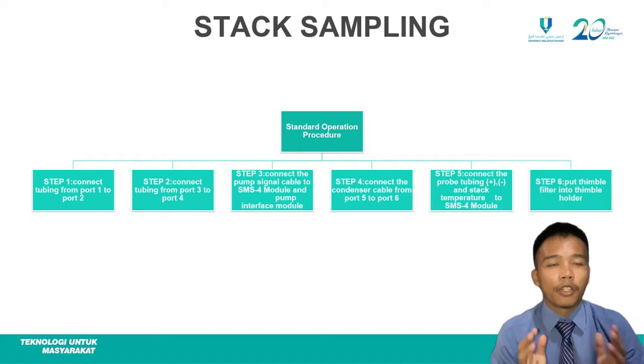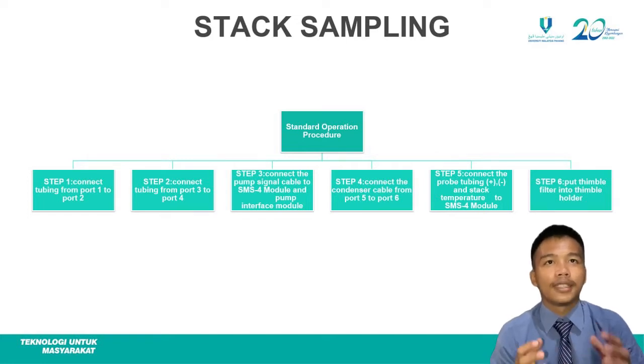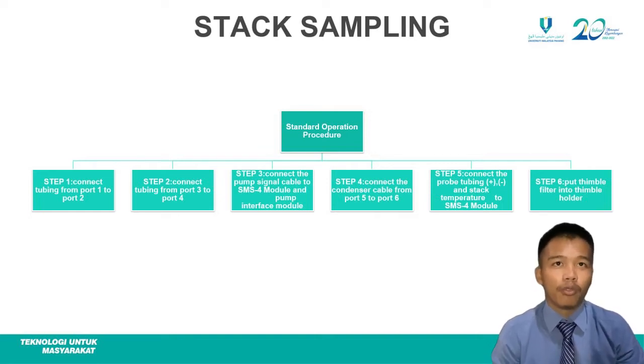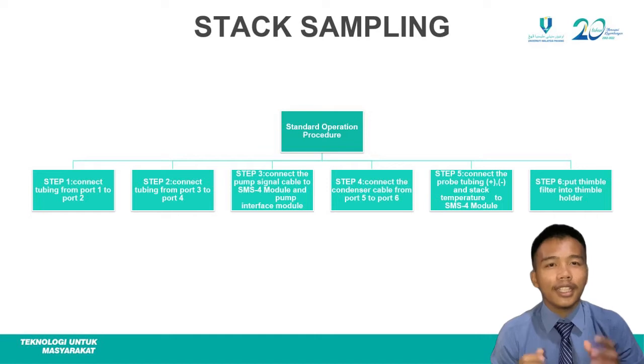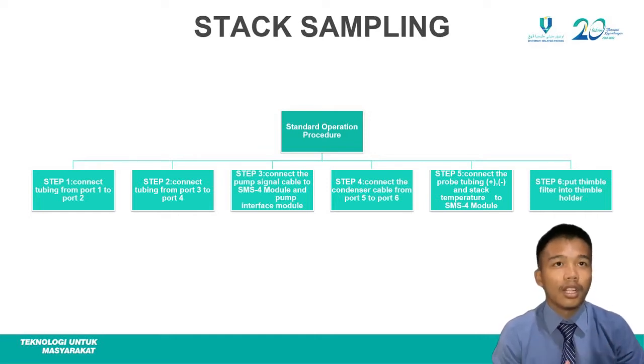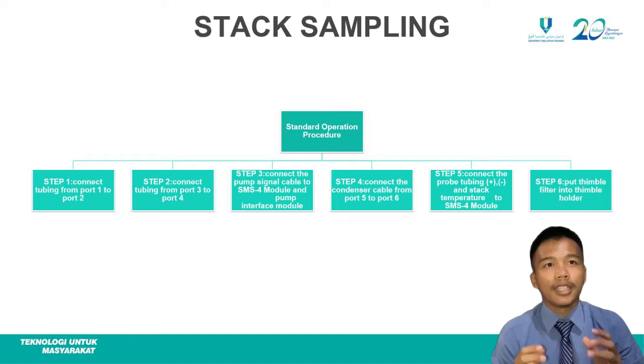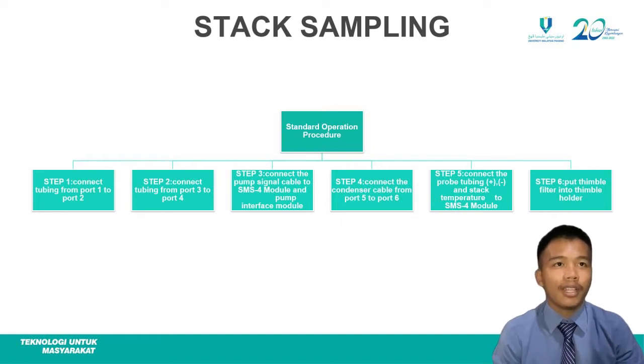Here is the standard operation procedure, or SOP, of stack sampling. The first one, connect tubing from port 1 to port 2, and then connect tubing from port 3 to port 4. Number 3, connect the pump signal cable to SMS4 module and pump interface module. And then step 4, connect the condenser cable from port 5 to port 6. And then step 5, connect the probe tubing, positive and negative signs, and stack temperature to SMS4 module. And the last one, step 6, put thimble filter into thimble holder.